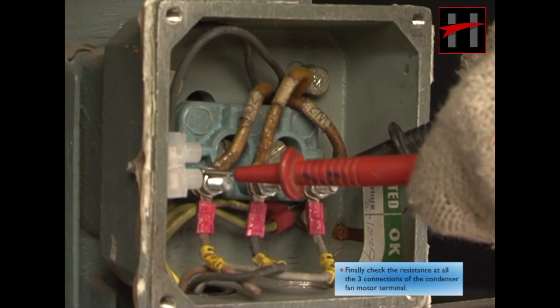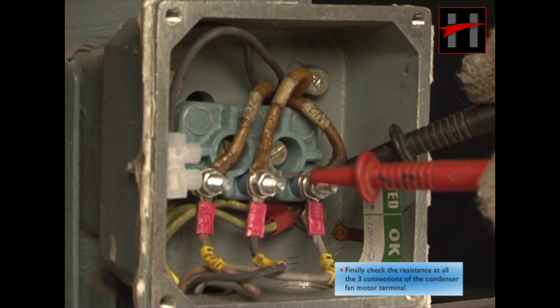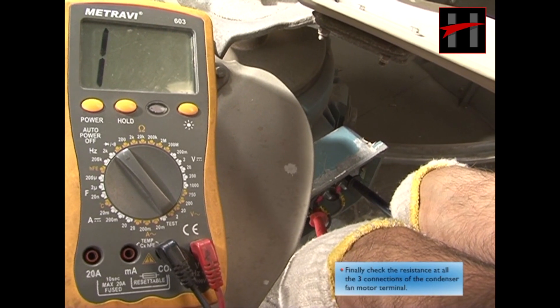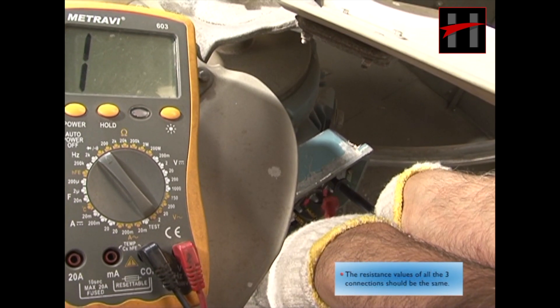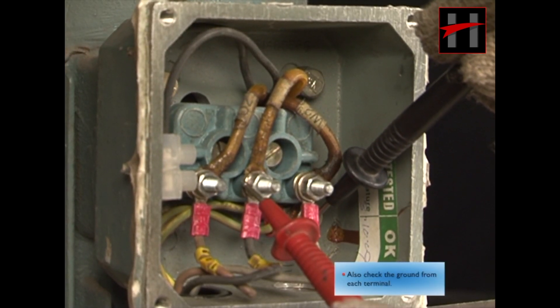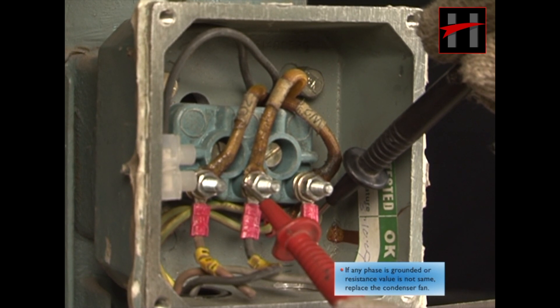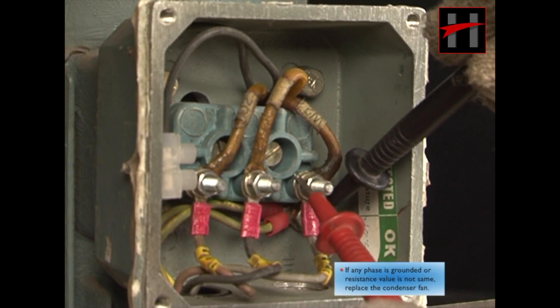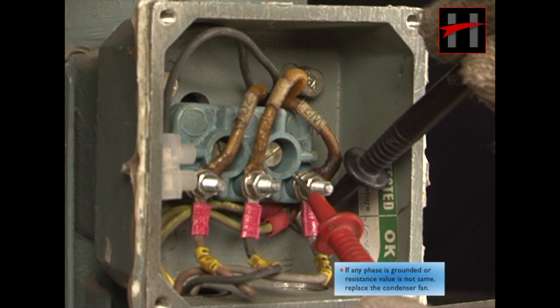Finally, check the resistance at all three connections of the condenser fan motor terminal. The resistance values of all three connections should be the same. Also, check the ground from each terminal. If any phase is grounded or resistance value is not the same, replace the condenser fan motor.